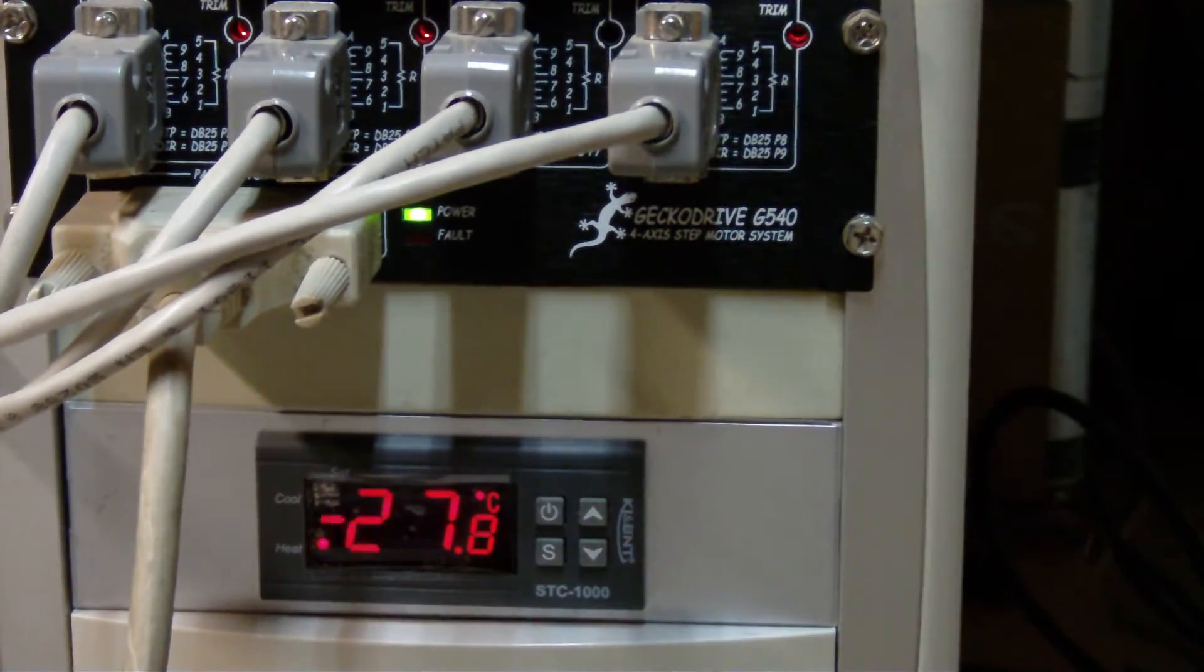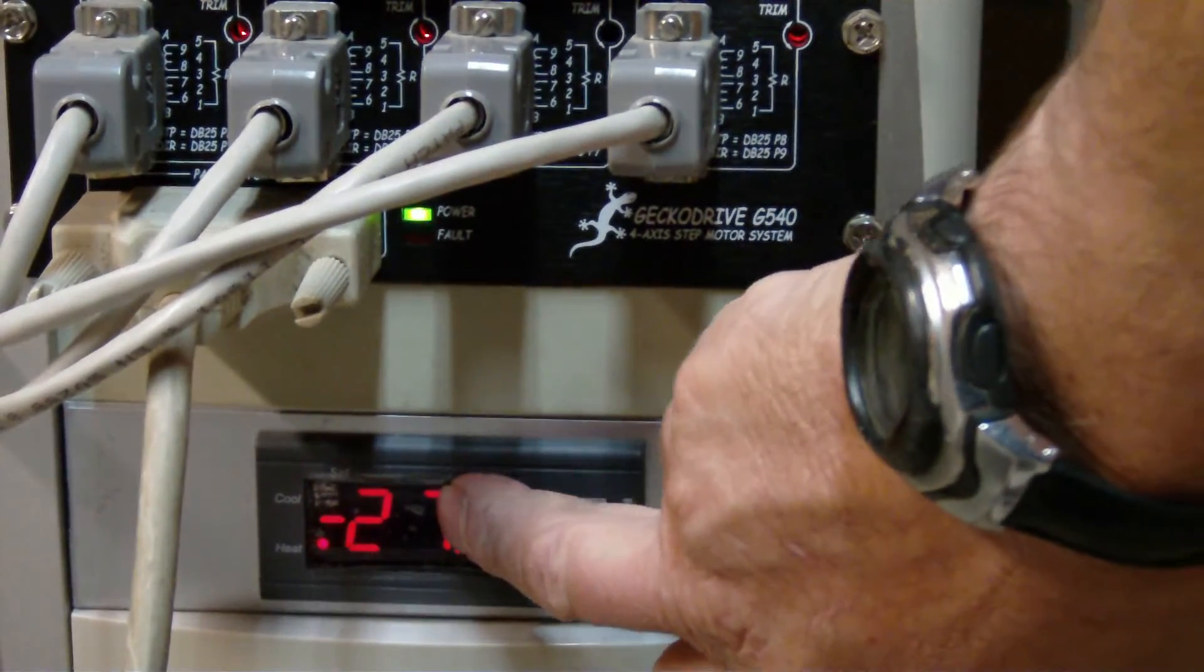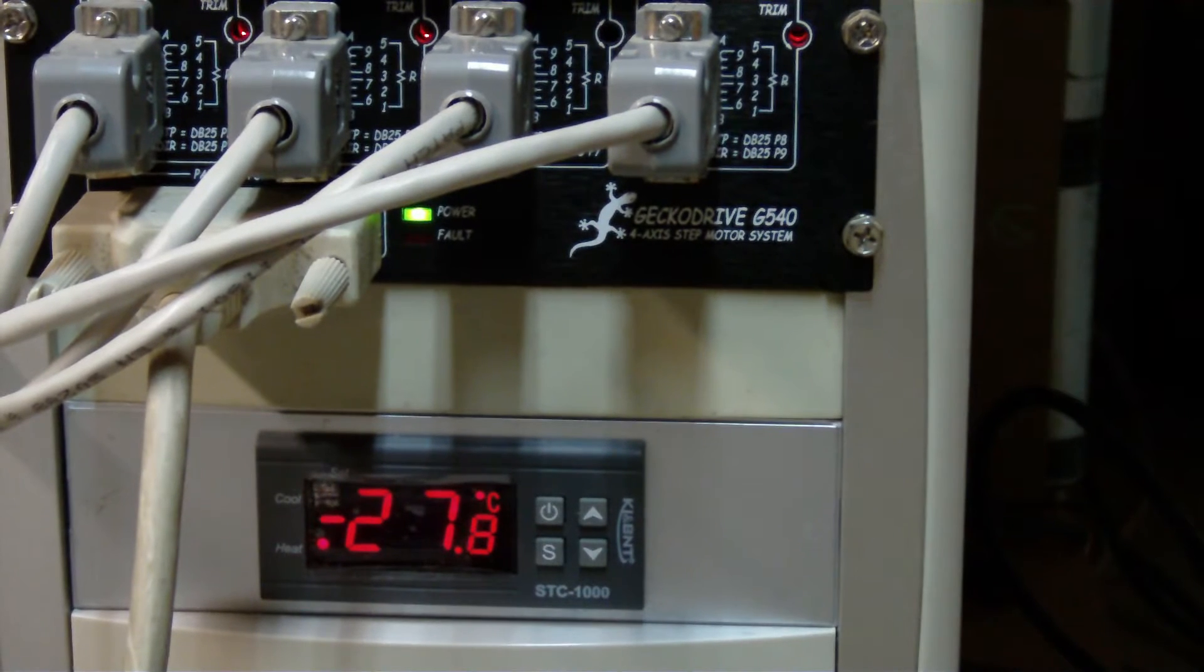Right I've just unplugged the sensor. You can see it's come up with a really strange reading. But if I leave it like that, if my cable breaks or what have you, within 60 seconds the unit will have gone into an error condition again and trip the emergency stop.